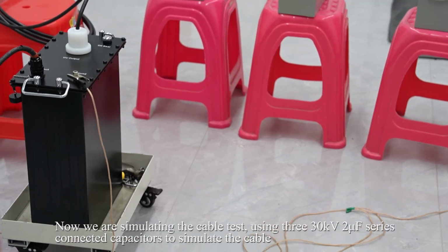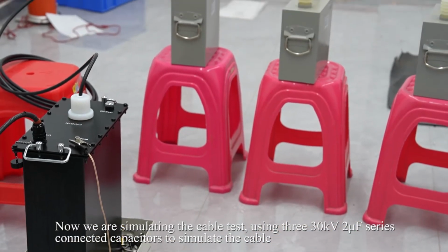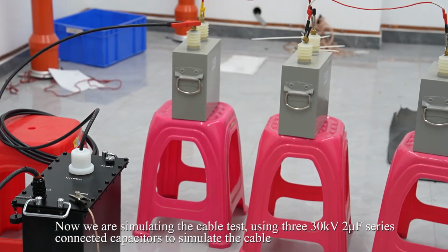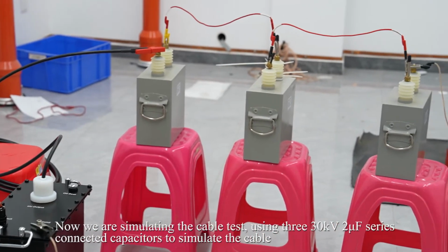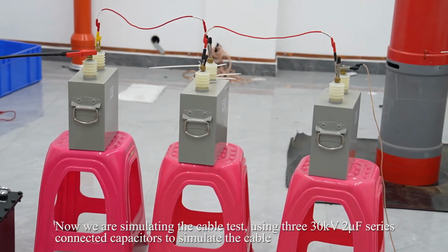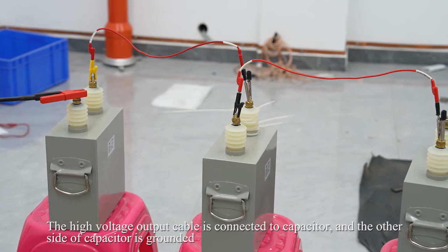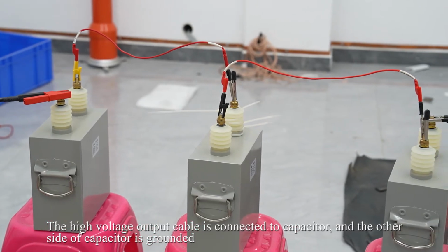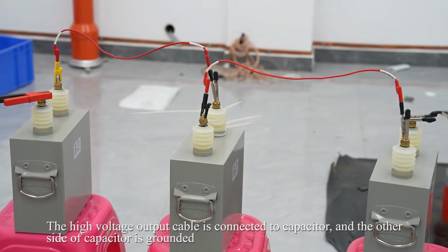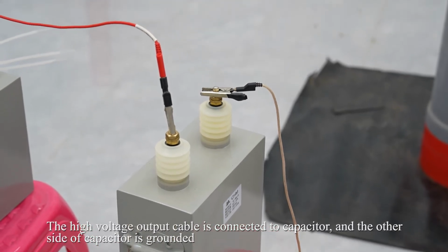Now we are simulating the cable test. We use 3 series-connected capacitors, 30 kV, 2 microfarad each, to simulate the cable. The high voltage output cable is connected to the capacitor, and the other side of the capacitor is grounded.